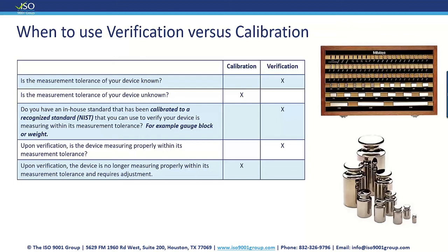It's calibrated. It's reading properly. It's within tolerance. That's verification. So why would I want to send that out just on a routine basis, on an annual basis, if it's reading properly? If somebody drops a device, yeah, we still need to go back and verify. If it's reading properly, there's no need to send it out for calibration because there's no adjustments needed.